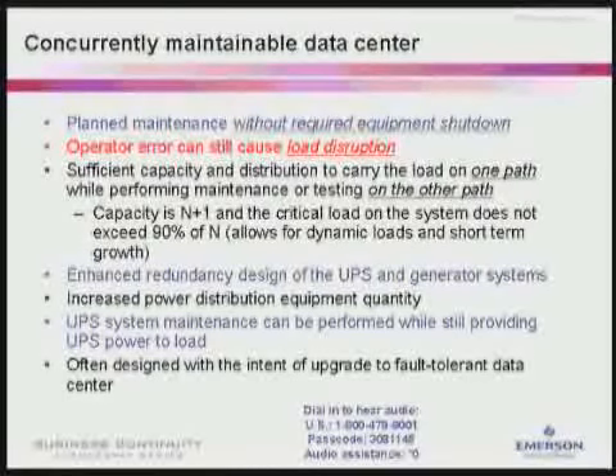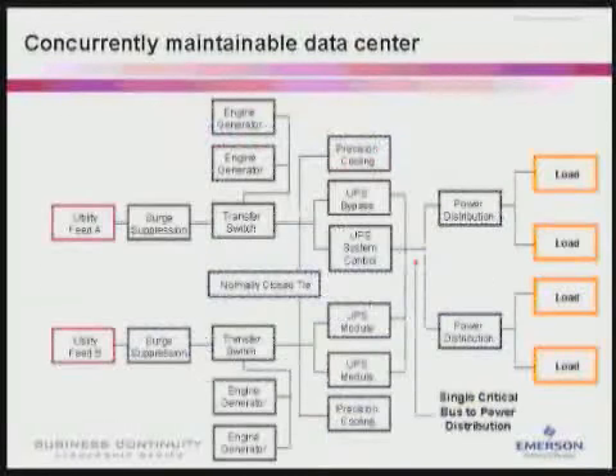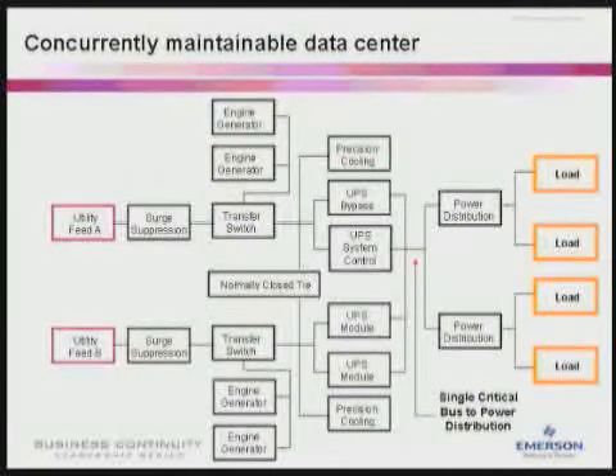Slide. Here is one line of a concurrently maintainable data center. It has redundant feeds, redundant engine gen, and transfer switches with precision cooling on the generator protected source, redundant UPS modules and maintenance bypass, separate power distribution paths to dual-corded loads, but a single critical bus to that distribution. There's a clear path to a fault-tolerant data center from one that is concurrently maintainable. Slide.